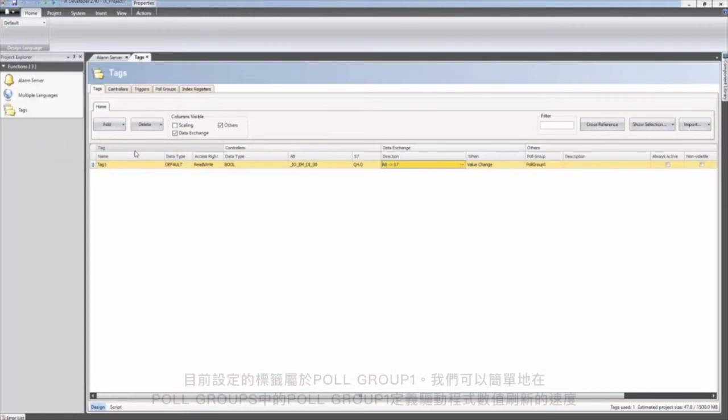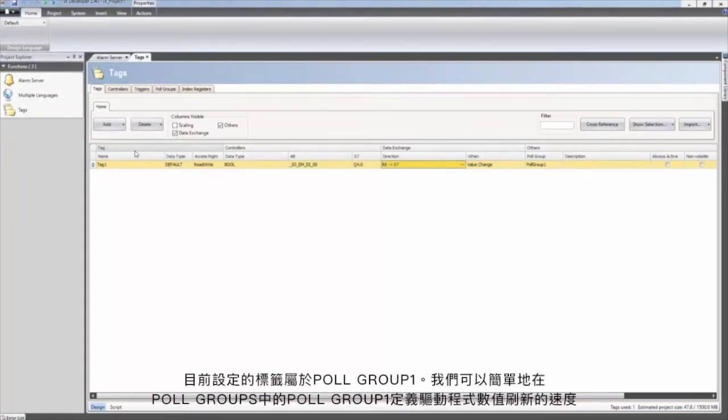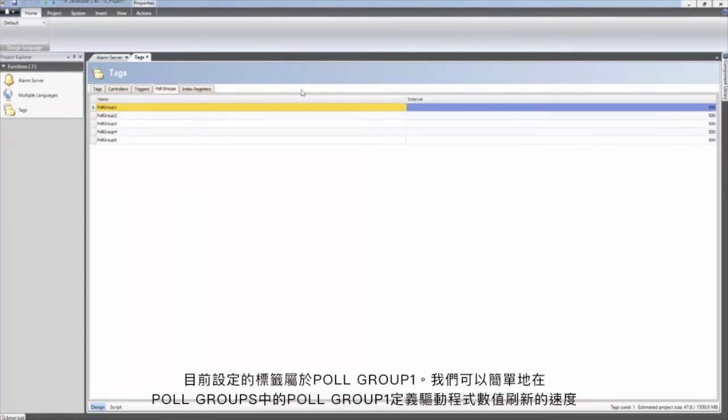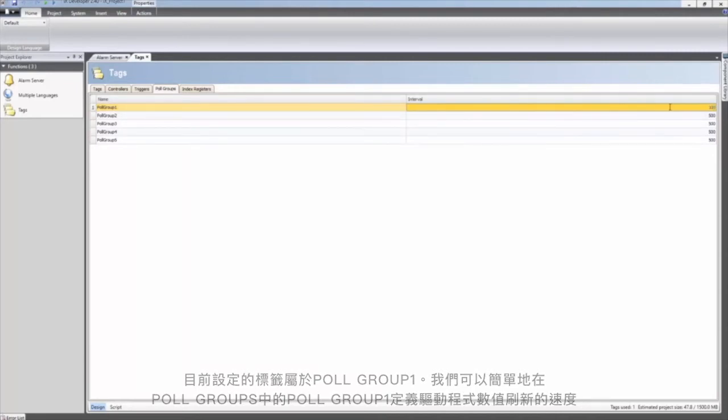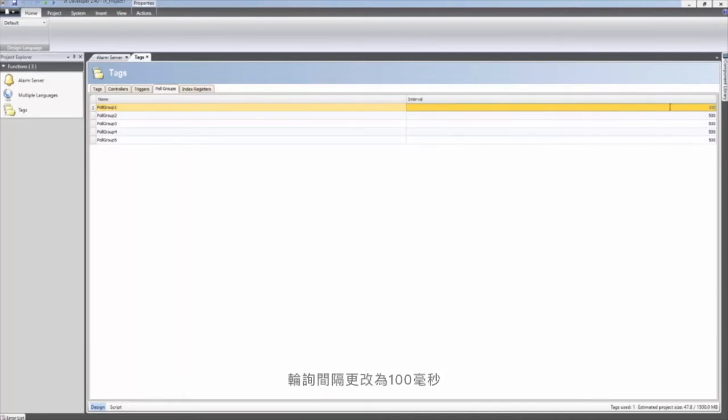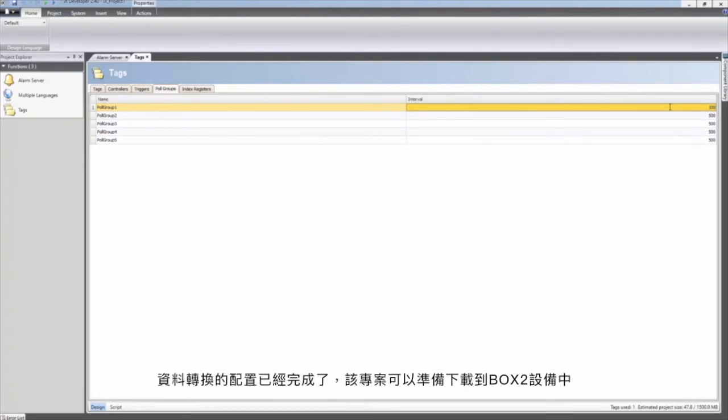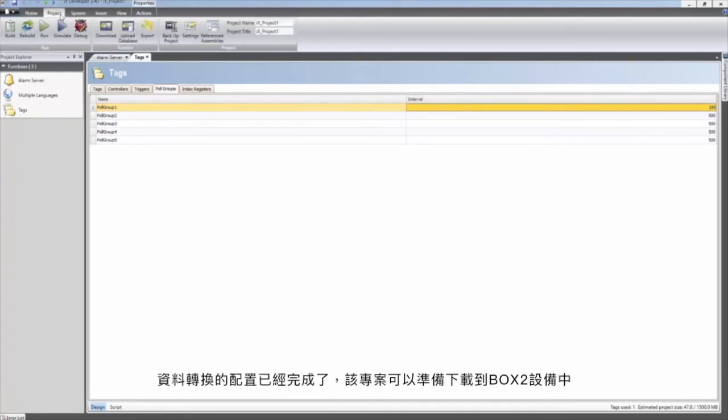The configured tag belongs to poll group number one. We can easily change how fast the driver should try to refresh the values. The poll interval is changed to 100 milliseconds. The data exchange is now configured and the application is ready to be downloaded to the Box 2 device. The transfer process is started by clicking the download button.